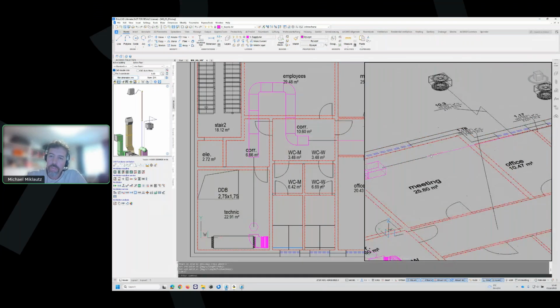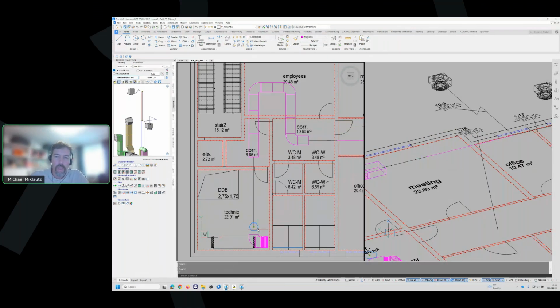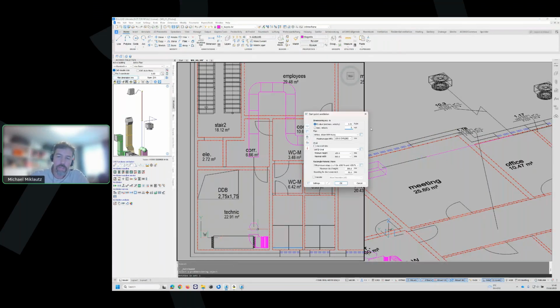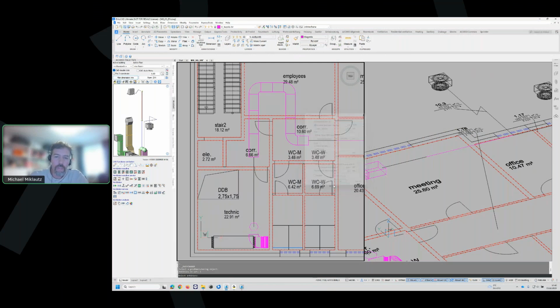This cross section will be used until the end of the line, and the software will be able to manage it if it should be larger or smaller because of the calculation values. To do this, I will raise the velocity to 5 meters a second.